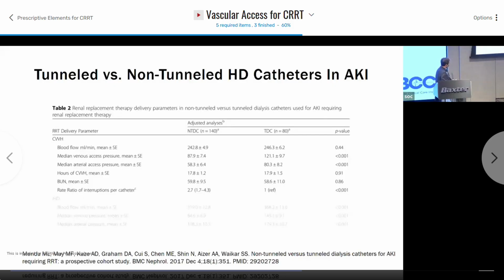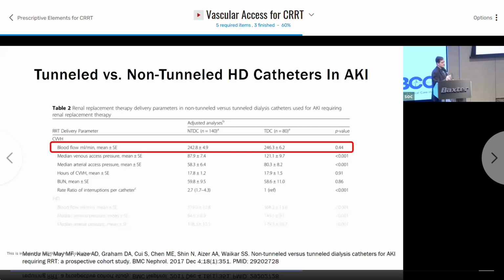The first thing to look at is blood flow. This is a calculated blood flow, or rather what it was set at, not the measured blood flow. As you'd expect, the program basically sets it all the same, about 250 in their program, so it's not different. That actually is a problem, because the short-term non-tunneled catheters are different in size and length from the long-term ones, so we're not really comparing apples to apples. And blood flows, if you actually measure them, are going to be different in those.